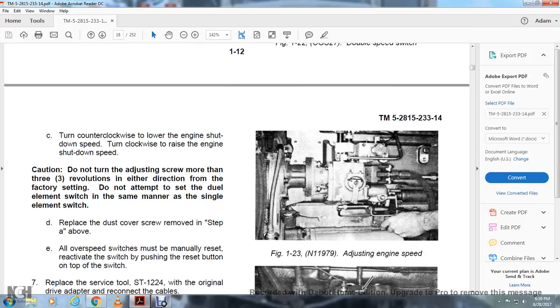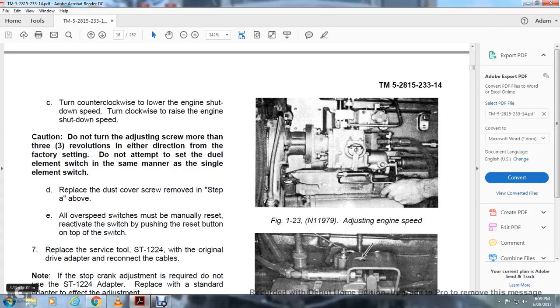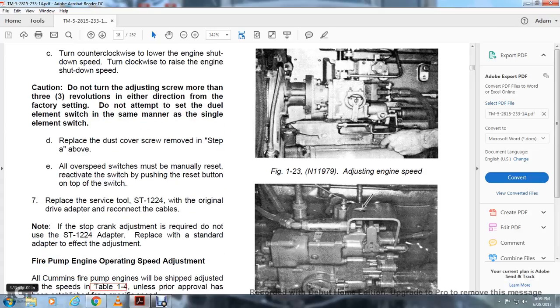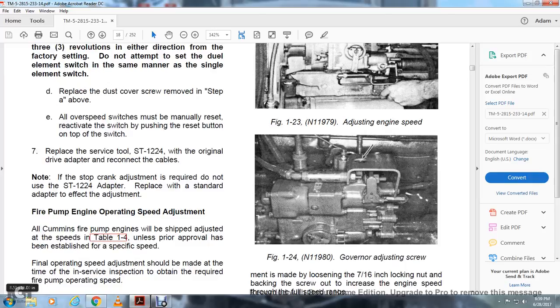Replace the dust cover screw removed in step A. The switch will work with all overspeed, but the switch must be manually reactivated by pushing the reset button on the top of the switch. Replace the service tool ST1224 with the original driver adapter and reconnect the cables. If the stop crank adjustment is required, do not use the ST1224 adapter. Replace it with the standard adapter to affect the adjustment.